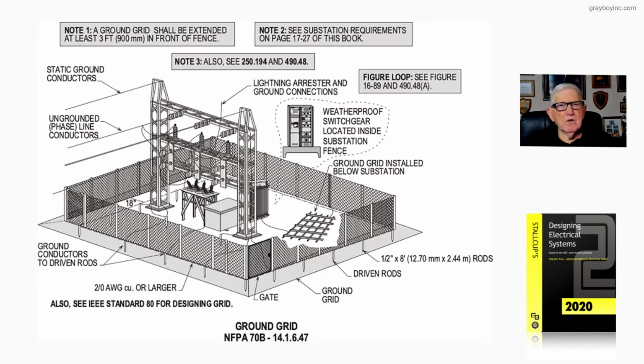Now let's look at Note 1. The ground grid shall extend at least 3 foot in front of the fence, and that's for step voltage problems. Where you're walking away from the substation, you wouldn't receive shock with steps. The IEEE Green Book, as well as the IEEE 80 book, gives us this information that you should extend it out 3 to 4 foot.